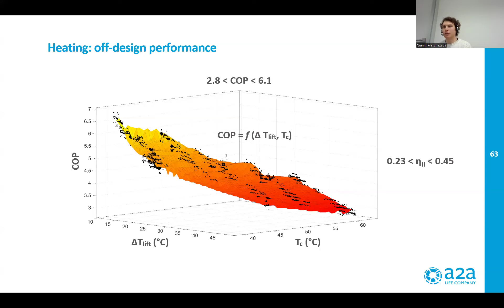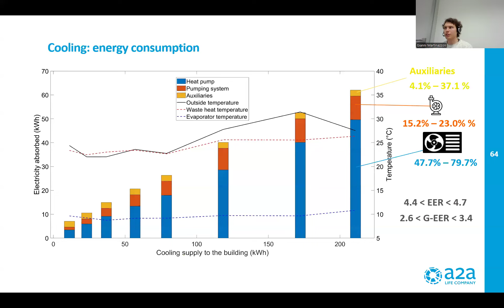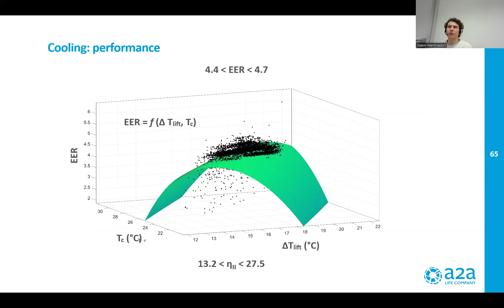We performed the same tests also in the cooling configuration, so using the heat pump as a chiller and providing the cooling demand of the building. So here you can see the electricity consumption of the main components of the substation, and we perform also off-design tests to evaluate the performance of the chiller in different operating conditions in terms of temperature, both at the evaporator and at the condenser of the chiller.